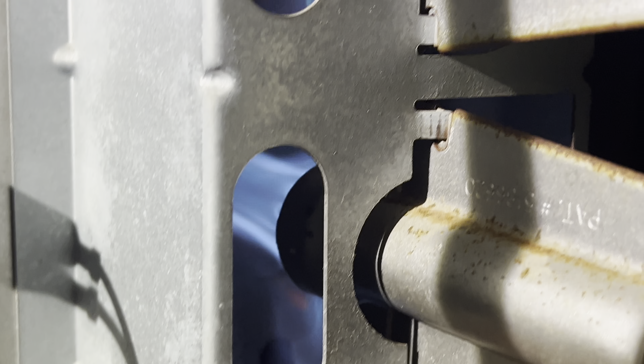Okay, so right now there's no flame rollout. Flame is burning good. Let's see what happens when the blower fan kicks on, because if there's a crack or a hole in the heat exchanger, it's going to roll out. The blower fan just turned on. And yeah, it's still looking good. Let me get the lights off. Yeah, that's burning good. No rollout.